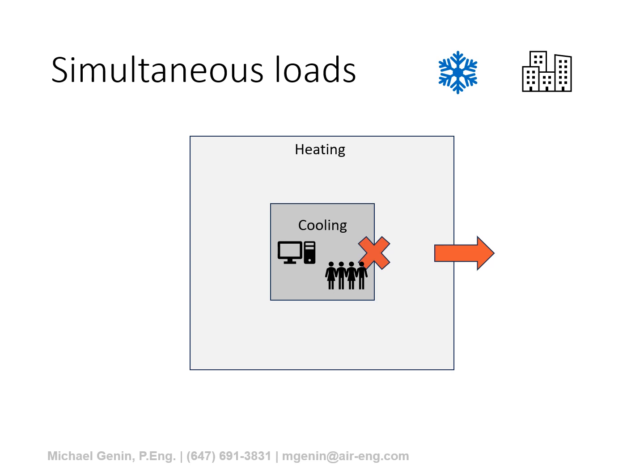This is because, in theory, the HVAC system is keeping the core zone at the same temperature as the perimeter zone. I mean, as you walk through an office building, it generally doesn't get colder and colder and colder as you approach the perimeter. Perhaps if there's substantial drafts around the perimeter of the facade, but in theory there's no heat transfer. So this interior zone is generating heat, but there's no way for it to exit through the envelope. So this zone actually requires cooling.